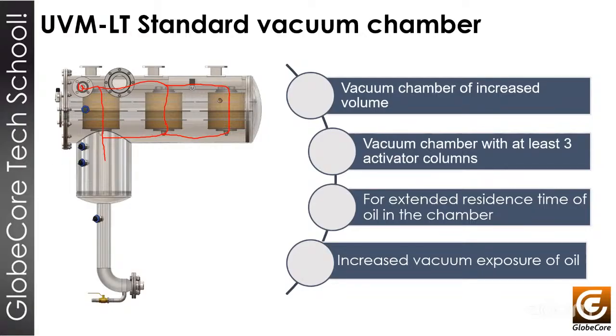That makes a lot of sense, if you know that when you have more exposure of the oil to the vacuum, you will have better results in the dehydration and the degassing process. Also, this vacuum chamber has different sensors for the different processes the machine will do. We have low level sensors. Here we have a high level sensor, and this sensor will protect against the formation of foam inside of the vacuum chamber. If this sensor activates, the machine will send us one alarm and will protect itself from this amount of foam inside the vacuum chamber.